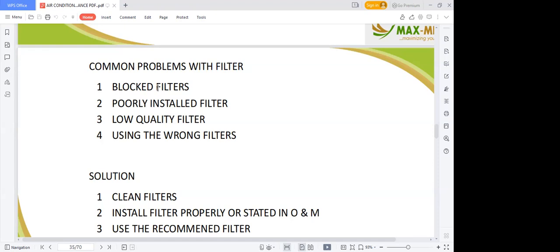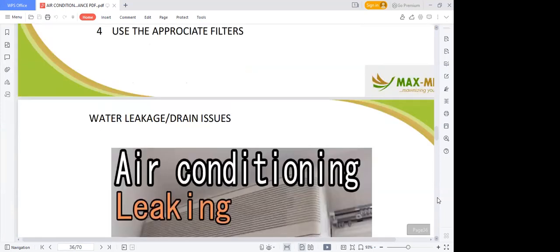There are some companies that spend so much to measure the quality of air within their space. They want to know what they are breathing. If you don't measure, you see that microorganisms fester in an environment that is dirty. And if it's dirty, your staff takes it in. Definitely, your HMO bills will keep going up because people will start complaining of similar disease. You understand? So what are the solutions? Clean the filter, install the filter properly as stated in your operational and maintenance manual, and use the recommended filter.